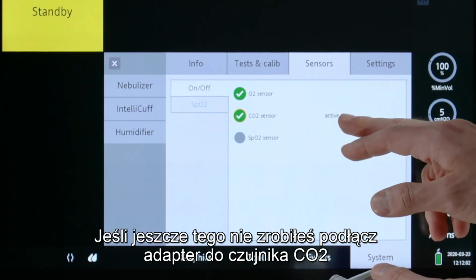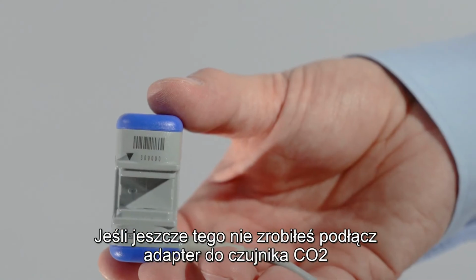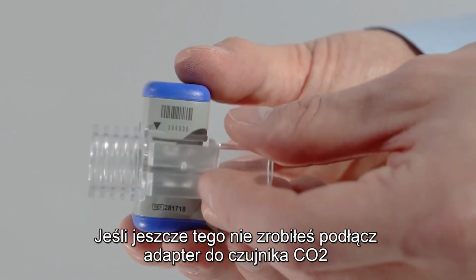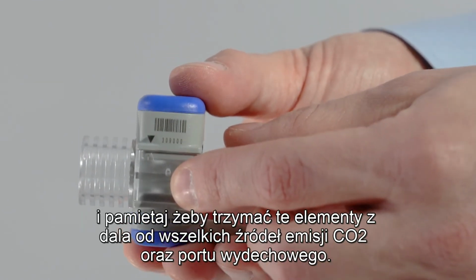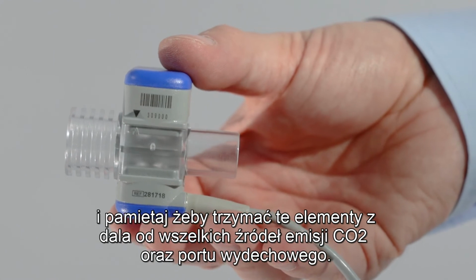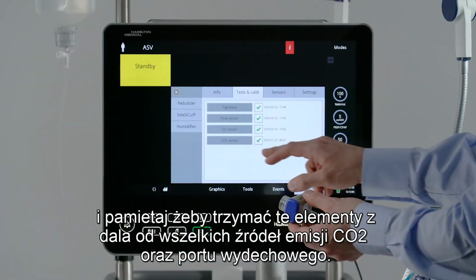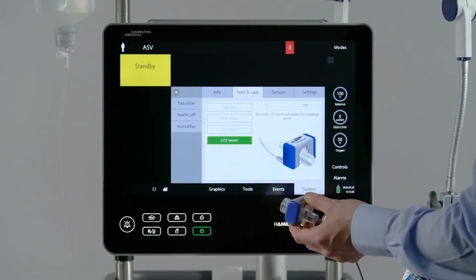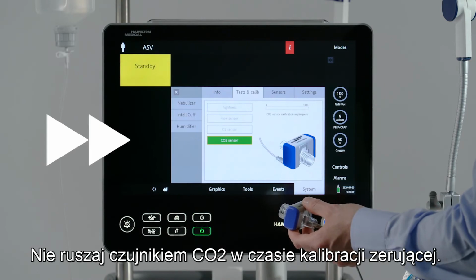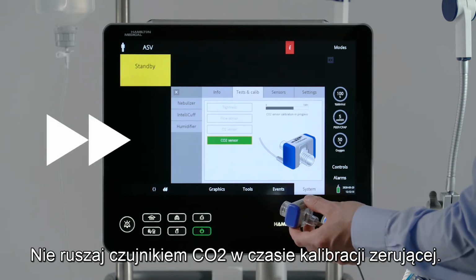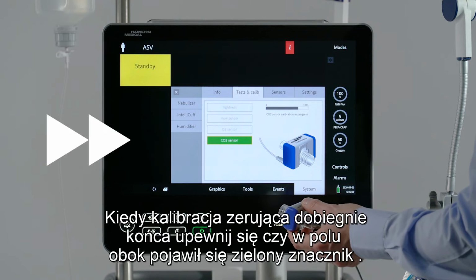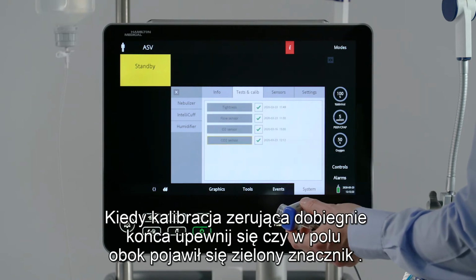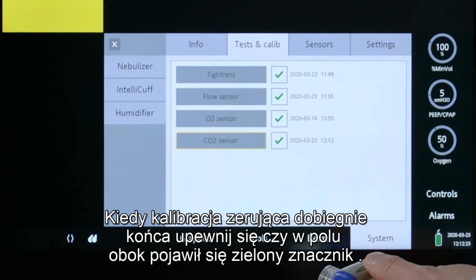If you haven't done so already, connect the airway adapter to the CO2 sensor and keep these components away from all sources of CO2 and the exhaust port of the expiratory valve. Do not move the CO2 sensor during zero calibration. When zero calibration is complete, make sure there's a green check mark in the CO2 sensor checkbox.